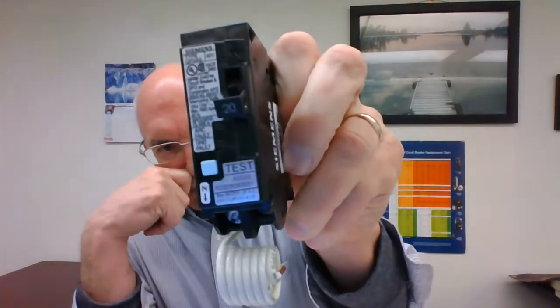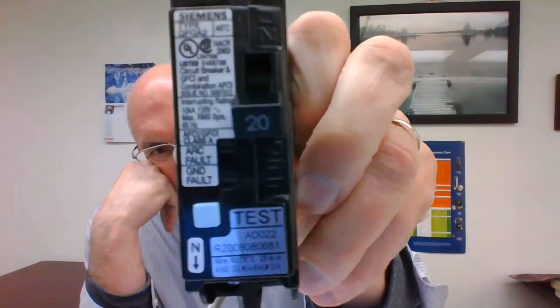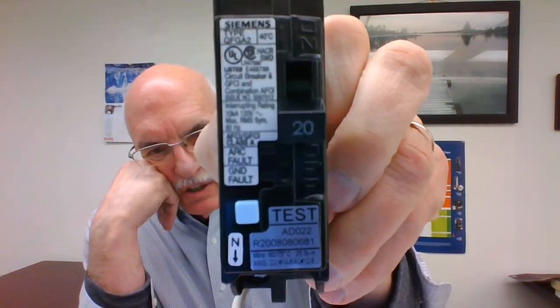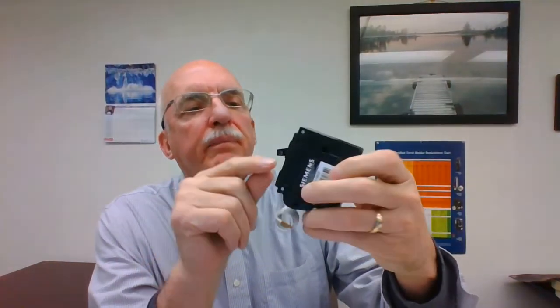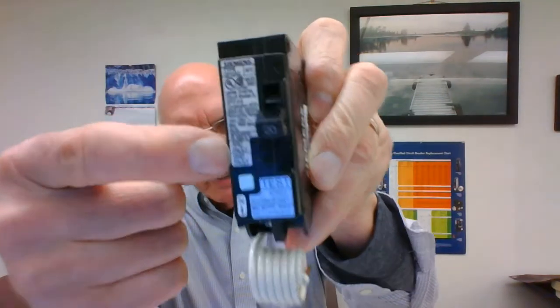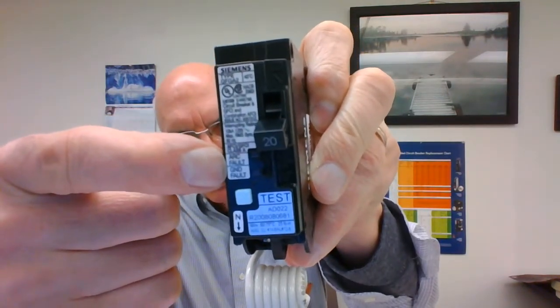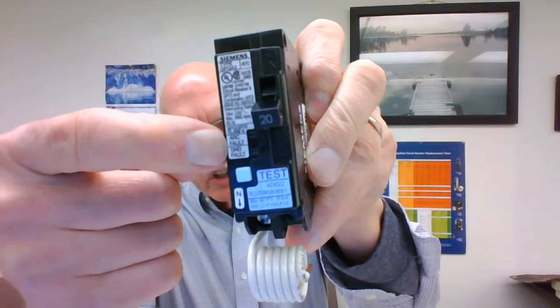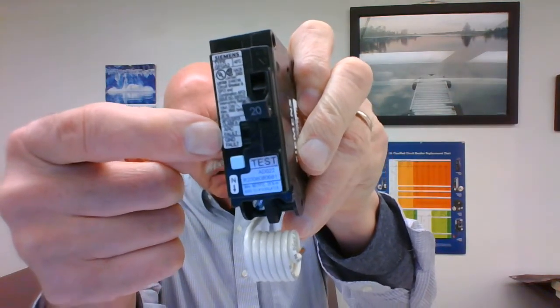Okay, this combination type says it right on here next to the handle, combination type. And this also has two different lights that would light up and tell you which type of protection this breaker tripped on, whether it was GFCI or AFCI. And we need that so that we can do our troubleshooting.